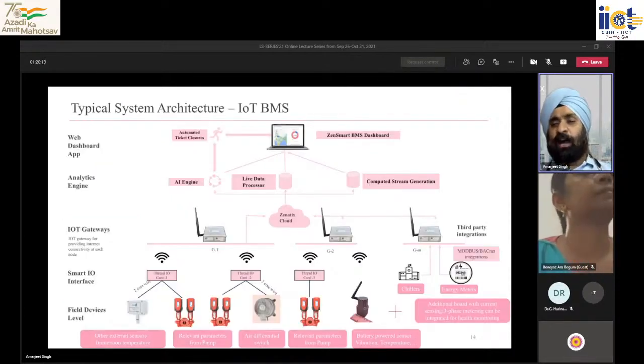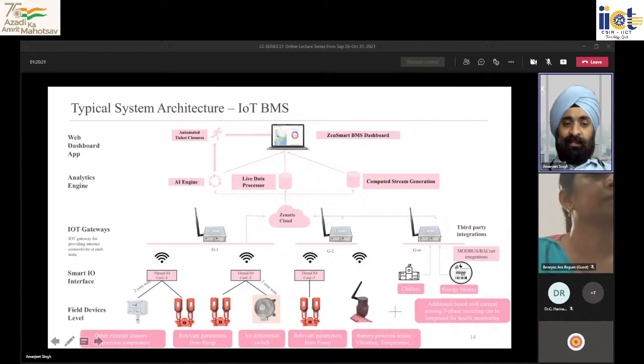So how are these things now coming together? There are, let's say, chilled water pumps, which are off the shelf, and an air differential switch, which is an off the shelf sensor. Both of these get connected to the wireless control card. The wireless control card, based on the air differential pressure, is controlling the pump, and is talking to the gateway over a wireless protocol.